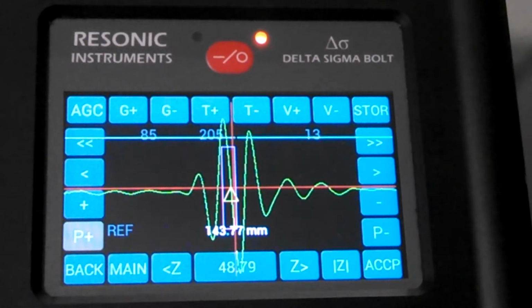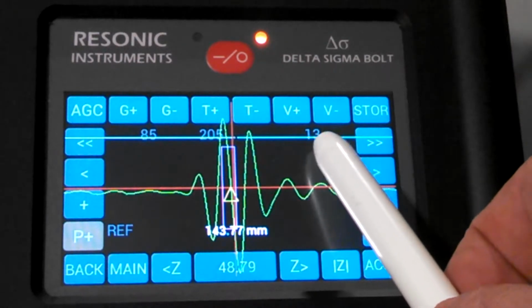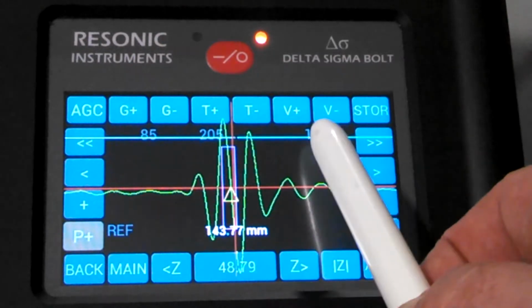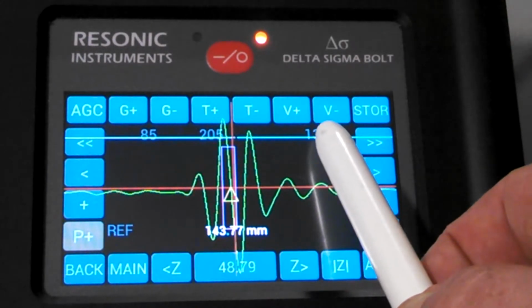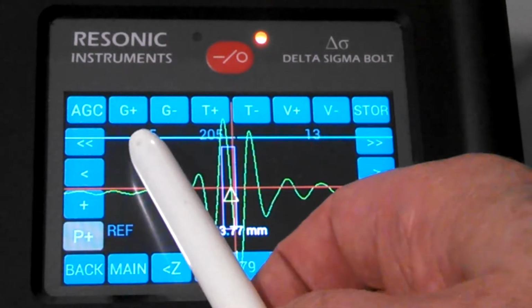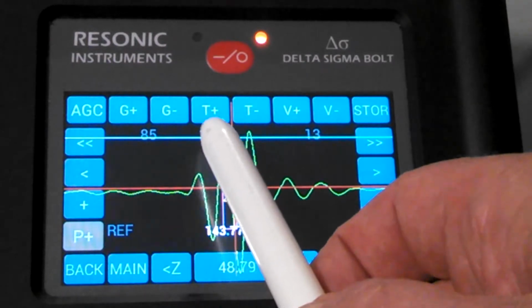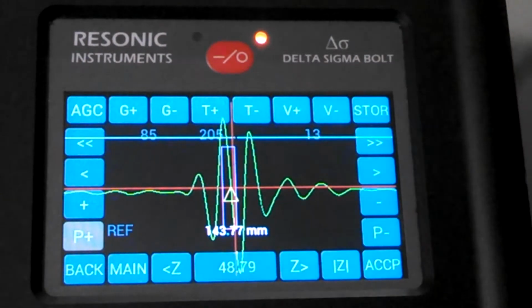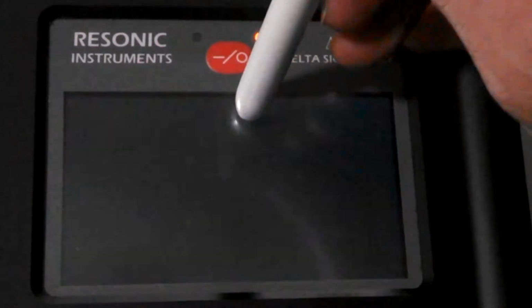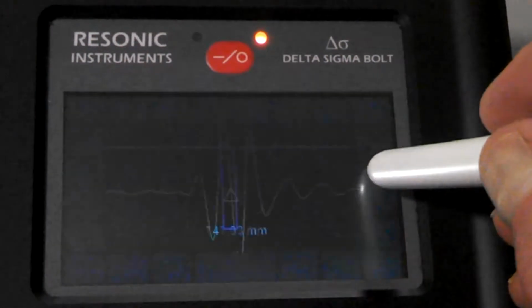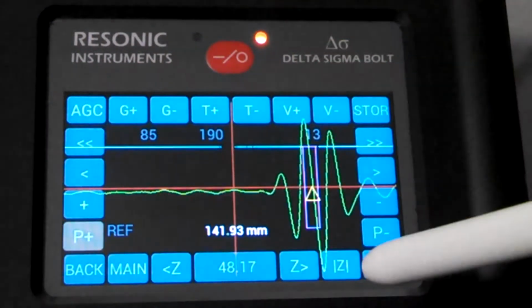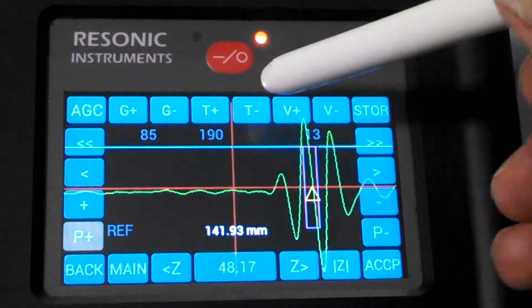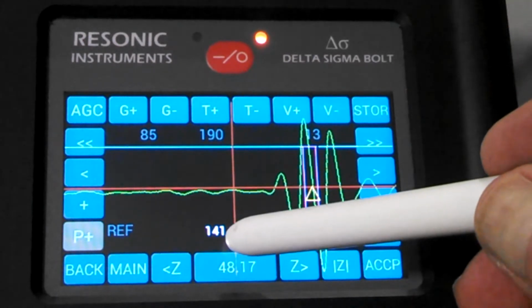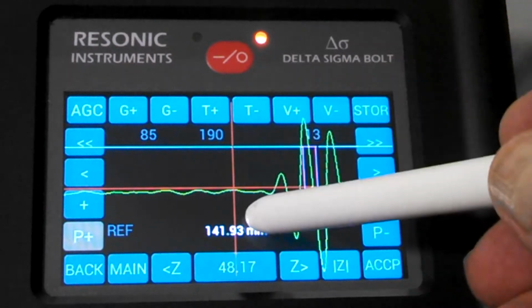So let's say you want to change something around on this. Our voltage count is 13, which is fairly low, so we're pulsing this probably around 10, 12 volts plus or minus. Our gain is 85. Our threshold is 205. If I want to lower the threshold, I hit the negative threshold, and you can see the threshold going down, 190. If I want to move the signal over so you can see it better, the carets move it. The double carets move it a screen away. The single carets move it just a few microseconds. The time on the bottom of the screen is the length to the center of the screen.